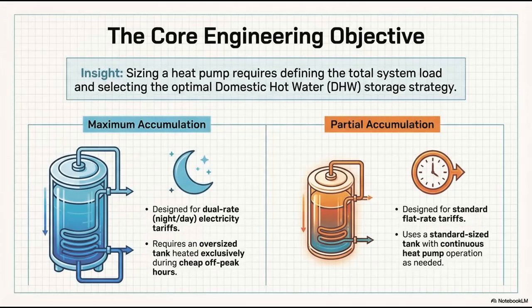I mean, this is the raw energy required to counteract the heat your house just naturally bleeds into the winter air. And what the engineering document makes crystal clear is that you don't just calculate the volume of air inside the rooms, you have to factor in the physical composition of the structure itself using these specific load factors. Okay, let's unpack this, because this detail stood out to me immediately. The document states that tall buildings with heavy concrete ceilings get a load factor of 0.90 applied to their calculation.